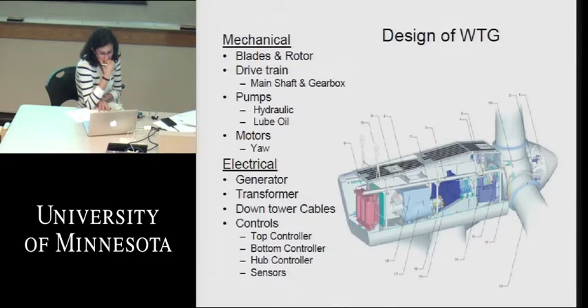To get the power from the transformer out into the collection system from the wind turbine, we have what are called down tower cables that take the full power from the generator, conditioned through the transformer, and deliver it to the collection system. The construction of these down tower cables goes along with the transformer, because it depends on where you're doing the transformation from low voltage to medium voltage. If you're doing it as shown in this picture, which should be component number 9, the red looking canisters at the back of the wind turbine, these are dry cast transformers that are located on top of the tower. They could be 300, 400 feet in the air.